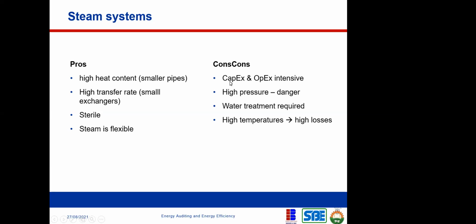Then what are the cons of steam? It's a very capital intensive system. It operates at a high pressure, which is a danger. And water treatment is required. If you're introducing water into your steam system, you need to treat that water. Otherwise, when the water evaporates, it will leave some residues that are undesirable in your steam system, which will definitely cause problems. Even though you must have treated your water before introducing it into the steam system, sometimes there is still residue, which is the reason why you need to do blow down, like I explained before. You need to do blow down to eliminate those residues.